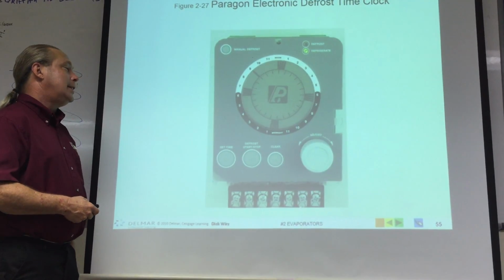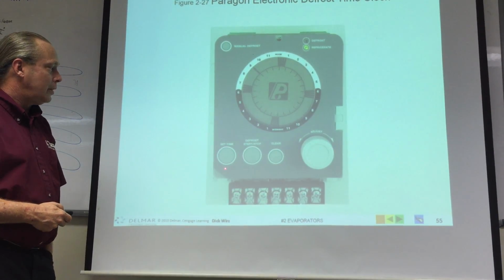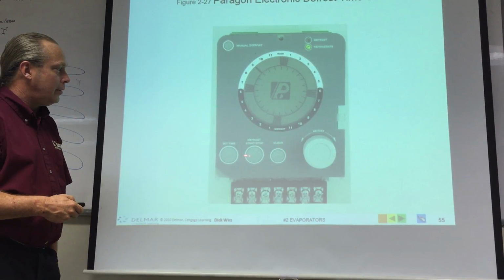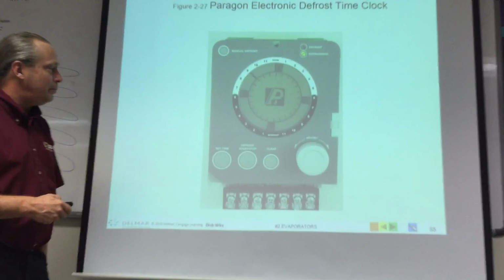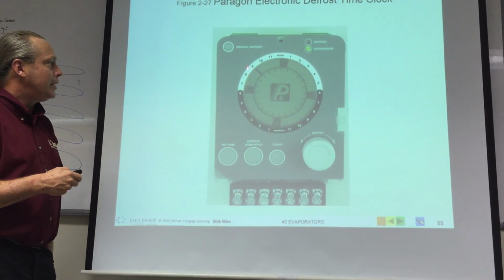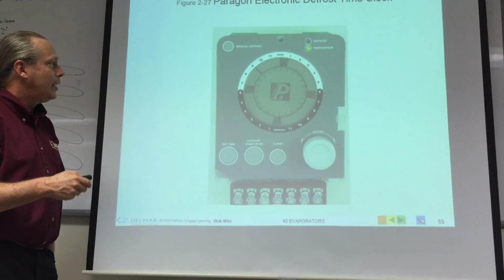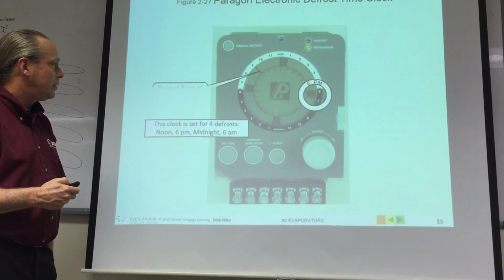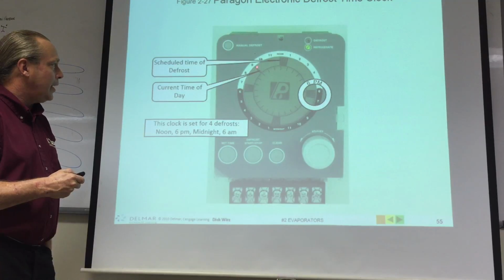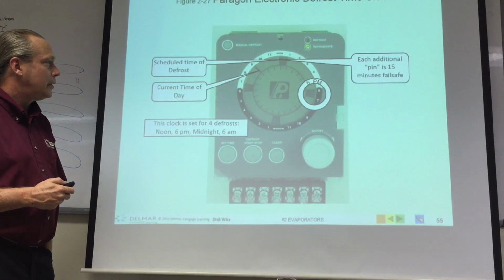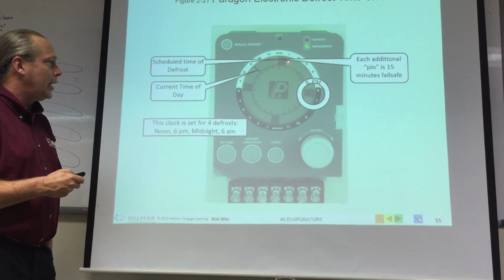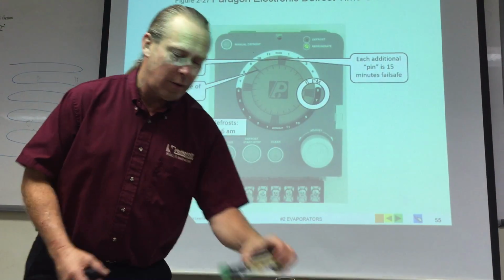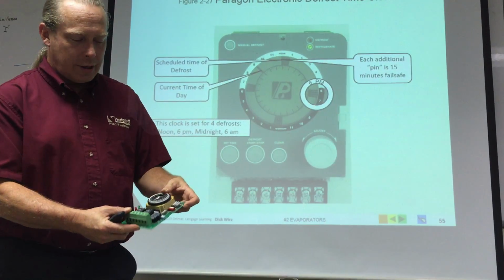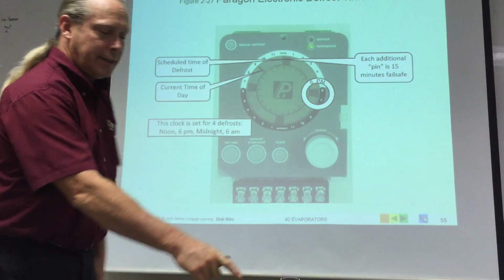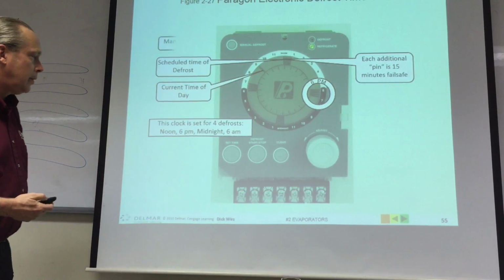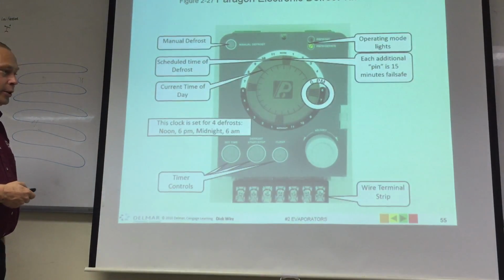Then they've got digital defrost timers. It's the same terminal strip. You come here, you set how much you want on, how much you want off. And there's the current time of day. Each one of these little things is 15 minutes. Same thing here. So in many ways, this is that model gone digital. Timer controls.